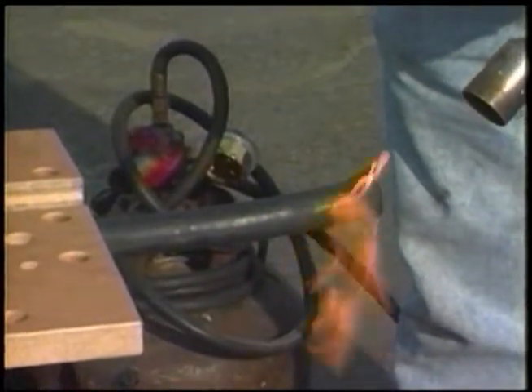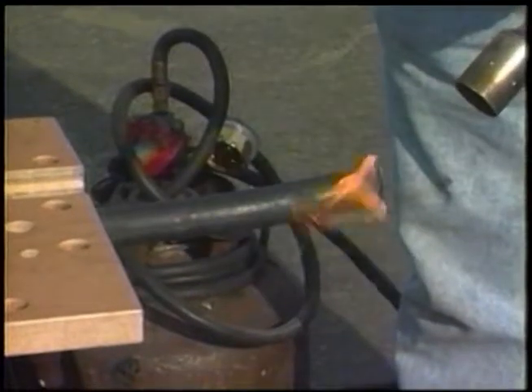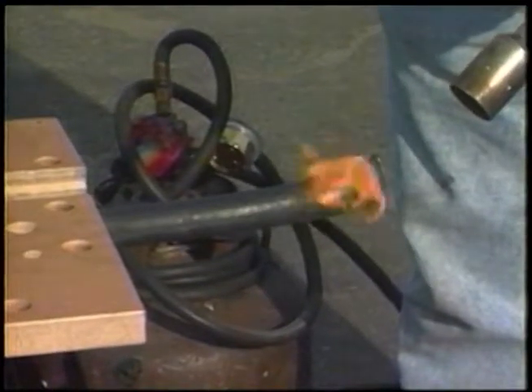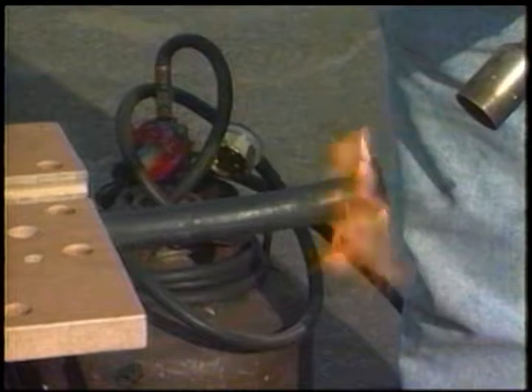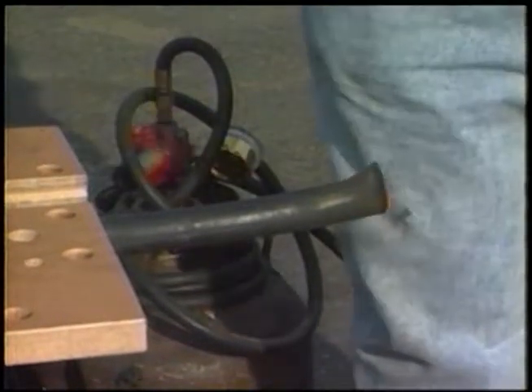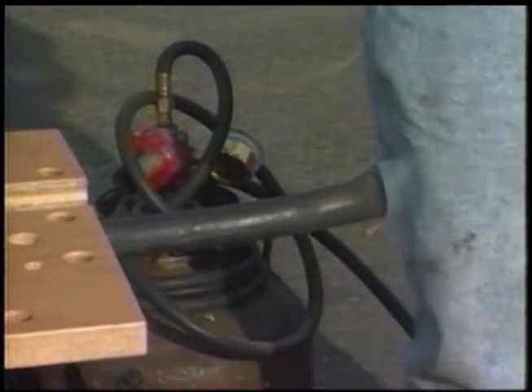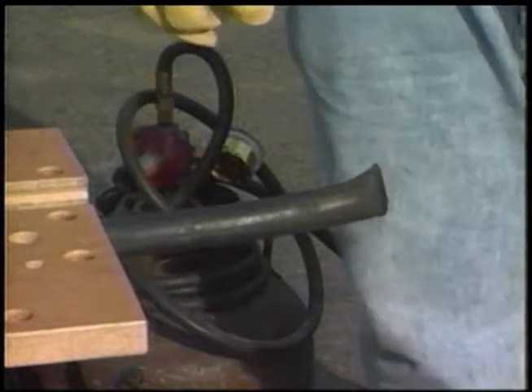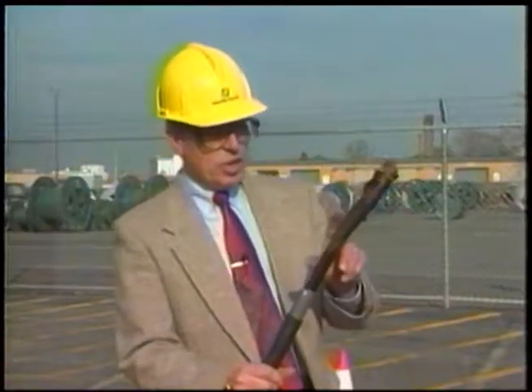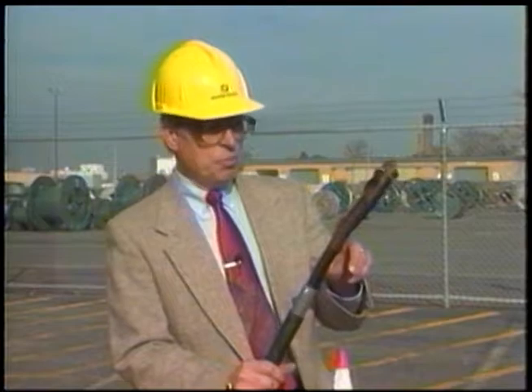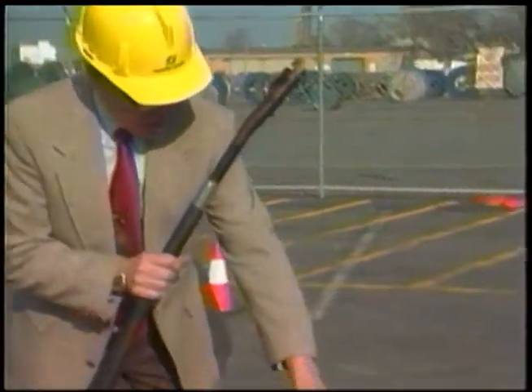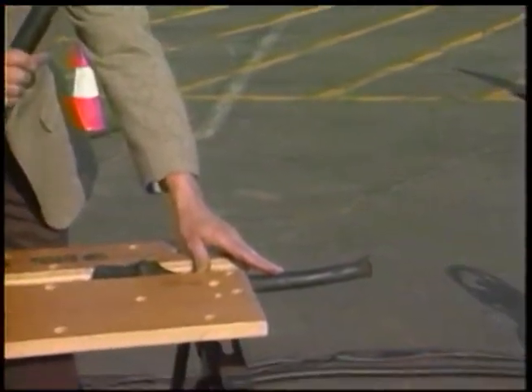Now we're burning it even more, a little bit more intense. We'll see if we can't get it going. With the flame on, it wants to burn. Now we take the flame off, and again, it wants to go out. In summary, the old paper and lead cable wants to burn, whereas the new cable that we install in manholes today does not want to burn.